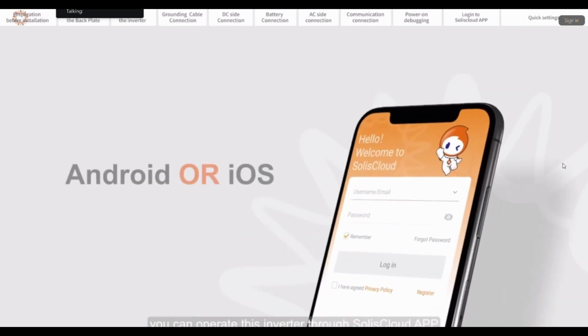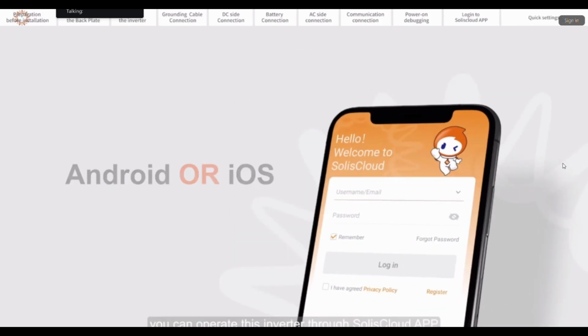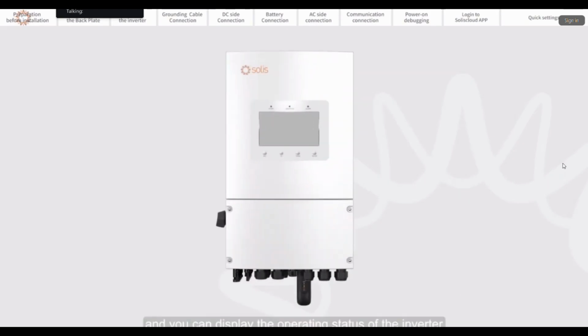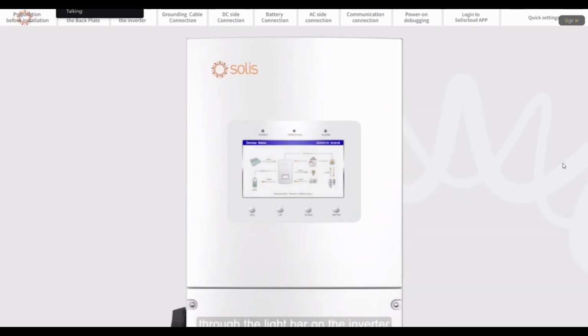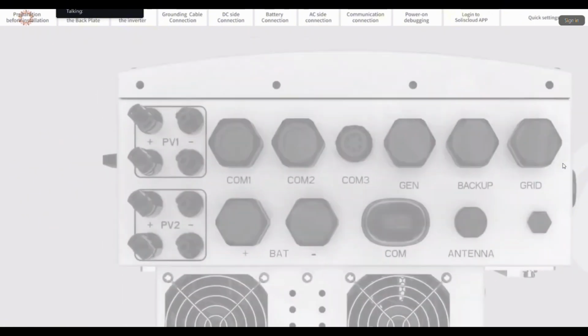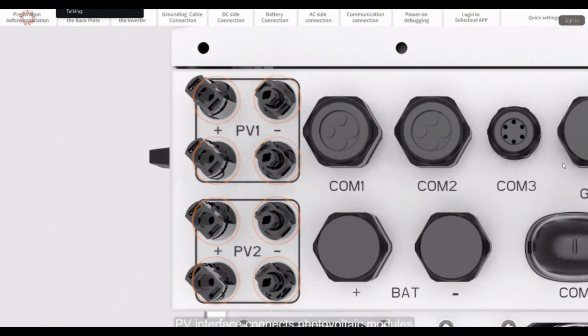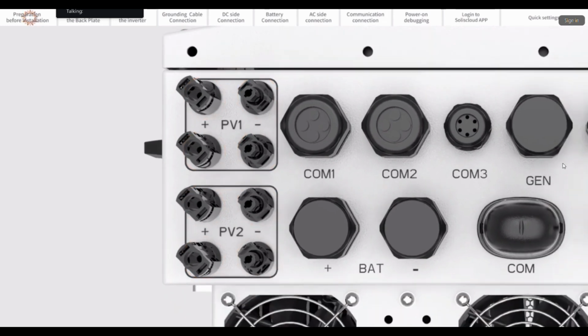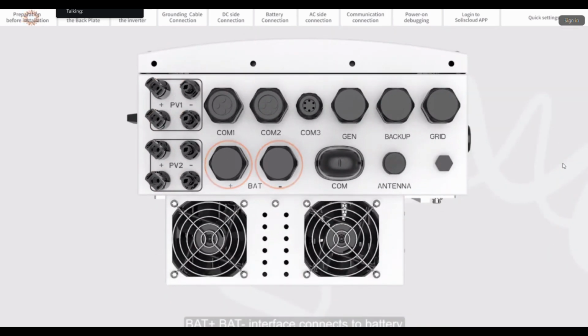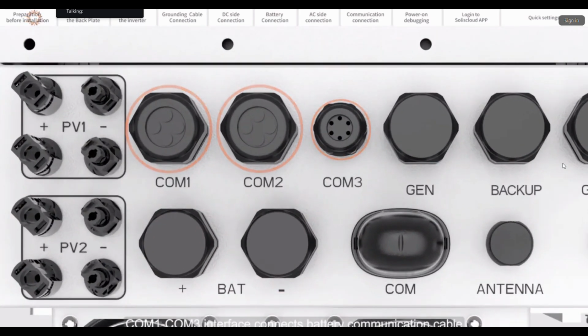Energy storage inverter adopts a new screenless design, and you can operate the inverter through the Solis Cloud app. And you can display the operating status of the inverter through the light bar on the inverter. The PV interface connects photovoltaic modules. Input photovoltaic energy into the system. BAT plus and BAT minus interface the battery. COM1 through COM3 interface connects the battery communication cable, the CT wire, the parallel cable, and the generator communication cable.